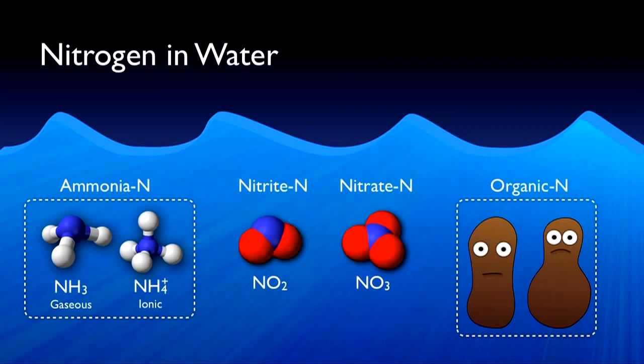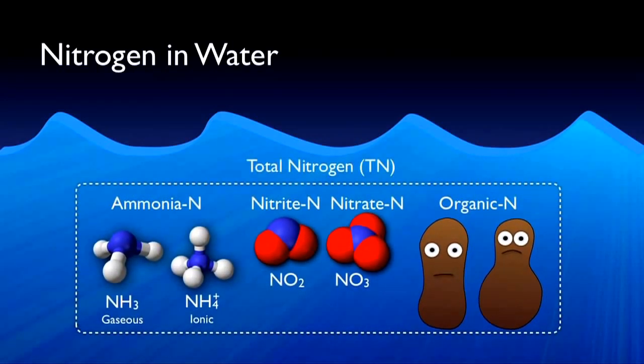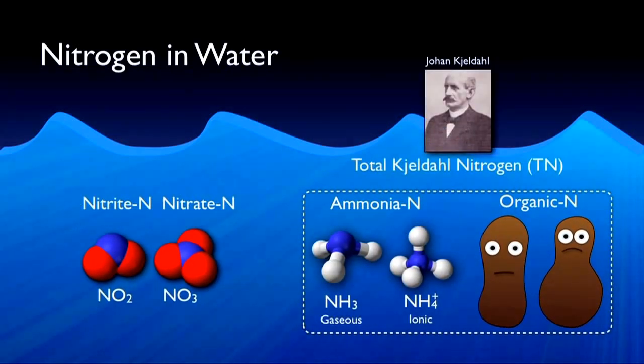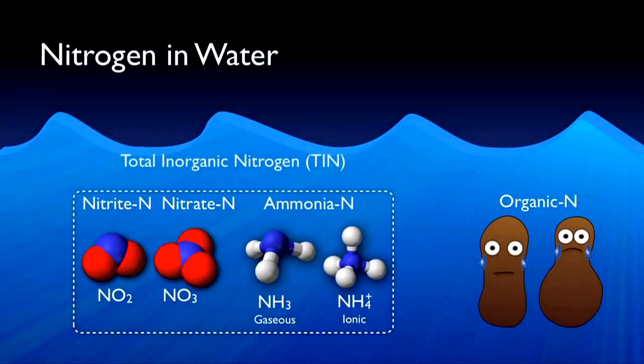A certain amount of organic nitrogen typically cannot be removed through the biological processes described in this video. Total nitrogen, as the name implies, is the sum of all types of nitrogen. TKN, or Total Kjeldahl nitrogen, named after the scientist Johan Kjeldahl, is the sum of only organic nitrogen and ammonia nitrogen. TIN, or total inorganic nitrogen, is total nitrogen minus the organic nitrogen.